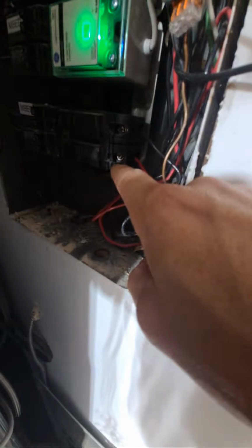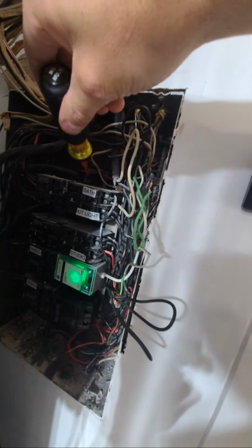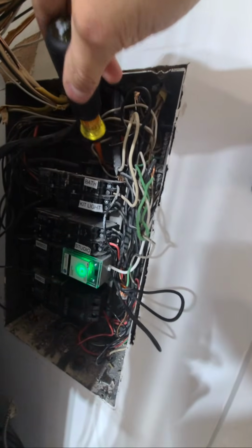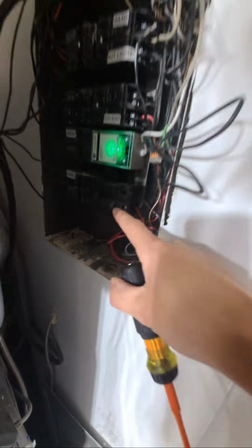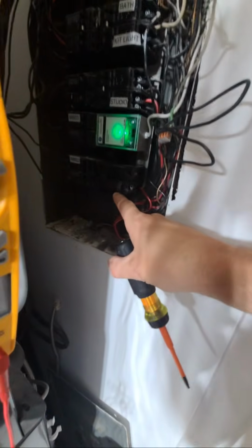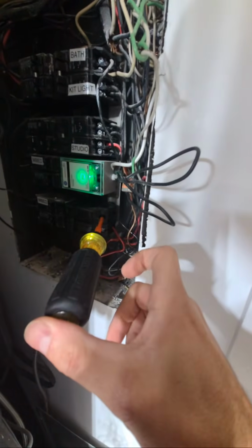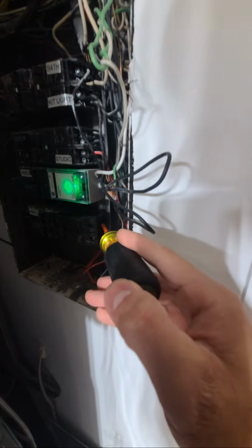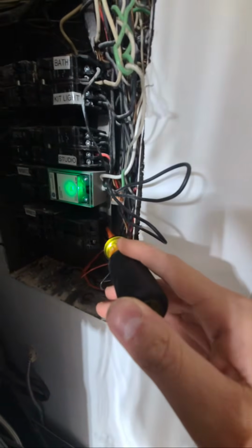So if you think your breaker's bad, you can go from this connection here all the way up to there. And that's going to give you a test on this screw, the bus, the breaker tab connection, the internal switch of the breaker itself, the tightness of this lug, the connection of this lug to the other side of the switch, and if your wire is even connected properly.